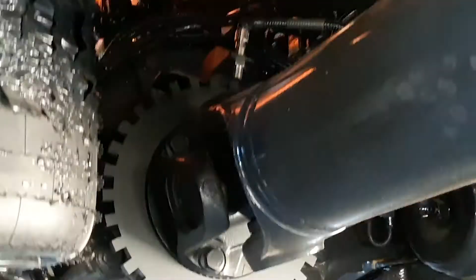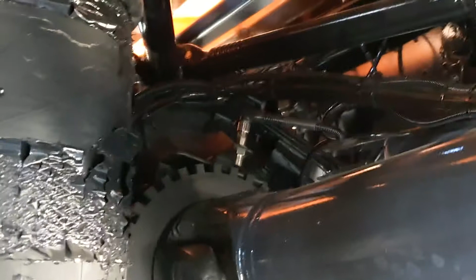We can see the sensor above. I'll take a closer look from the inside. So in the middle of the screen we can see now how we have installed the tooth wheel on the drive shaft and the sensor above. This holder will also be delivered together with the wheel shaft. You may have to make some small adjustments in order to make sure that the sensor is not more than 4 millimeters away from the drive shaft. So 4 millimeters is the maximum distance that this sensor will detect.